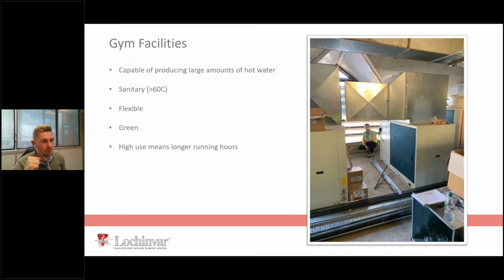One of the really powerful things about this is that your air source heat pump is now in an environment which, whenever I've gone into a plant room, is like the hottest room in a building. So you've created a simulated environment where the air source heat pump can run really efficiently. That's incredible, because it means the average temperature is going to run at something like 7 degrees.